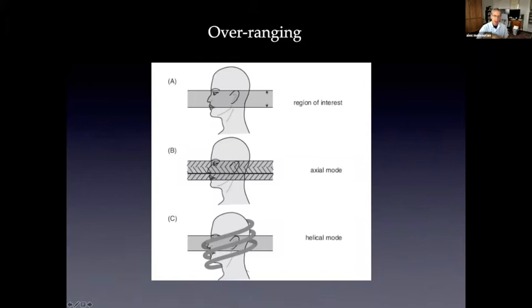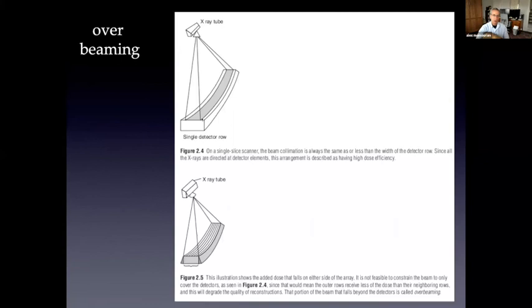So what is overranging? If this is the region of interest, if I want to cover that in axial mode, I cover exactly that volume in my trajectory of the beam. But if I'm going to go in helical mode, because of interpolation, the beam always has to start outside of the image volume and end outside of the image volume. And depending on the scanner and the detector array width, this may actually cover a lot of tissue that is outside of the region of interest. So this is adds to the inefficiency of multi detector scanner.